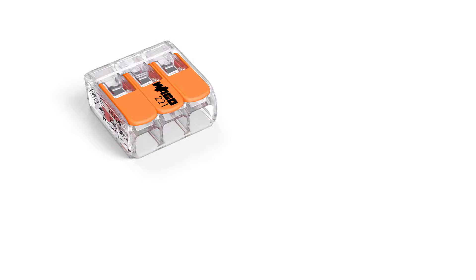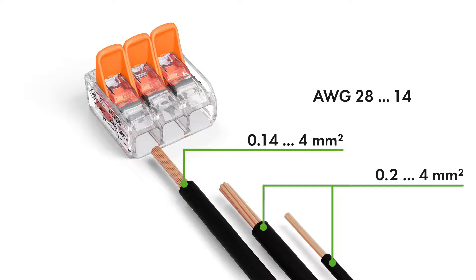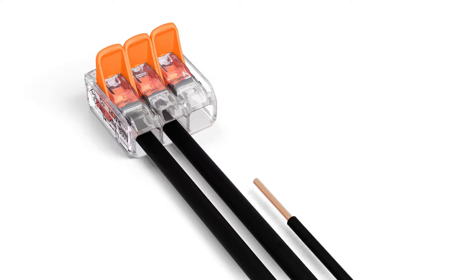The compact splicing connectors for all conductor types feature a large connection range, 0.14 to 4 square millimeters fine-stranded and 0.2 to 4 square millimeters solid and stranded, 28 to 14 AWG. This flexibility permits a wide range of applications, especially when conductors of different types and different sizes are used together.